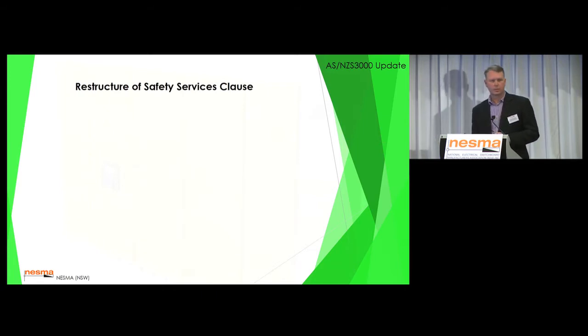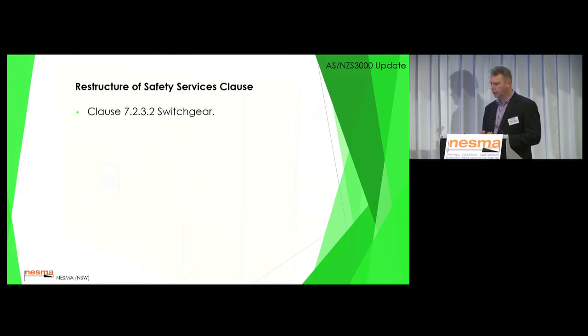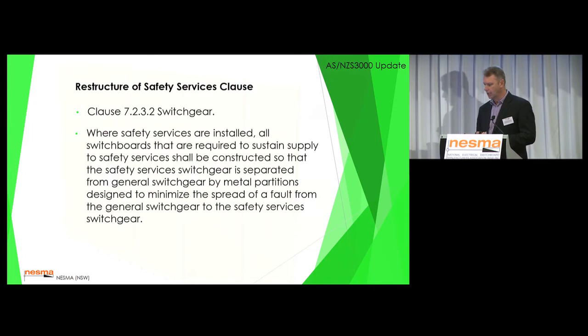Restructure of the safety services clause. This is only a small one, but I think important to a lot of people. Clause 7.2.3.2, switchgear. Where safety services are installed, all switchboards that are required to sustain supply to safety services shall be constructed so that the safety services switchgear is separated from the general switchgear by metal partitions.